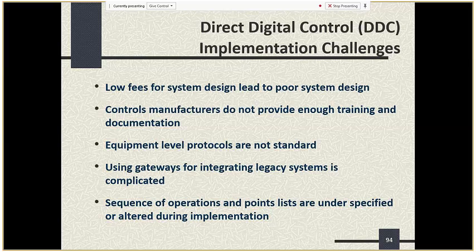Have you found that integrating that Trane equipment into the JCI system has been fairly straightforward, or do you run into gateway issues? It was relatively straightforward in this project, and I only say that because the equipment was relatively new. Where this becomes a problem is when you're trying to address a system that's 15, 20 years old, it becomes much more problematic. Oh yeah, absolutely.